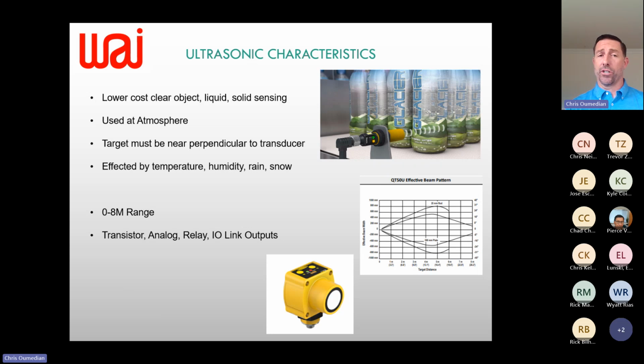Very loose powders would absorb a sound wave. They must be used at atmosphere, not in a pressurized tank, or you kind of mess up those sound waves. Another thing to be aware of with an ultrasonic is the target needs to be perpendicular to that sound wave. If you look at the bottles there, it needs to be perpendicular.